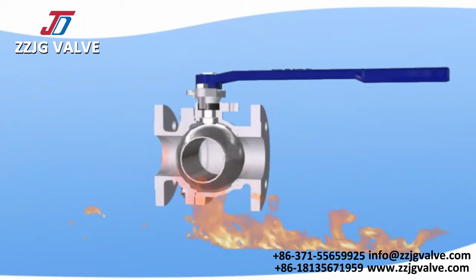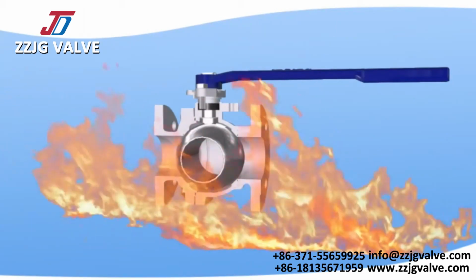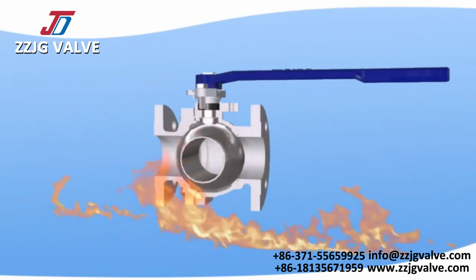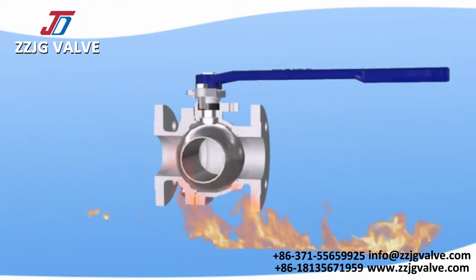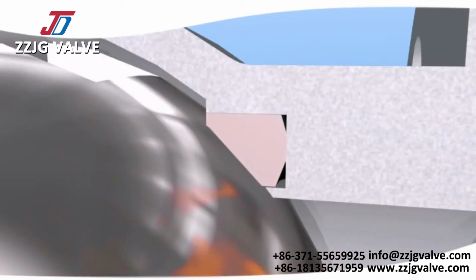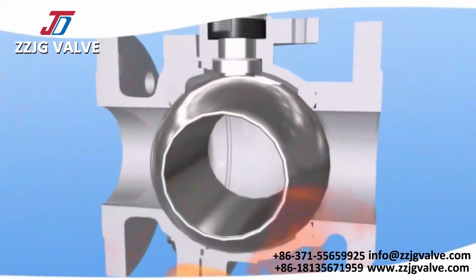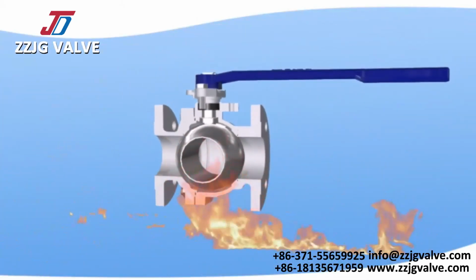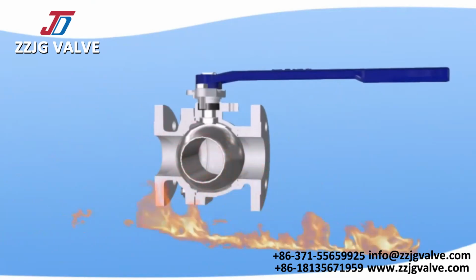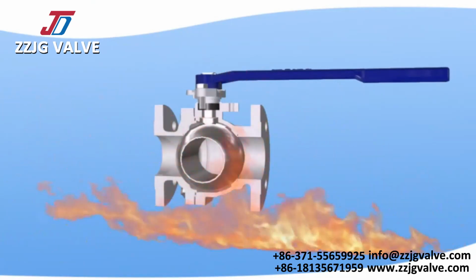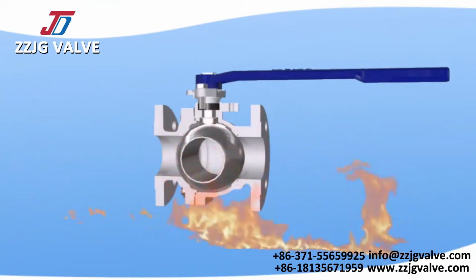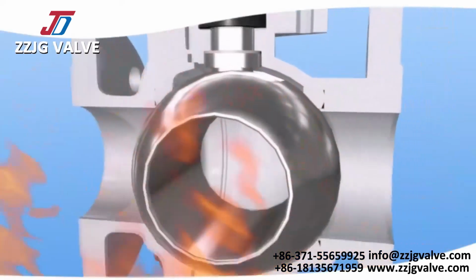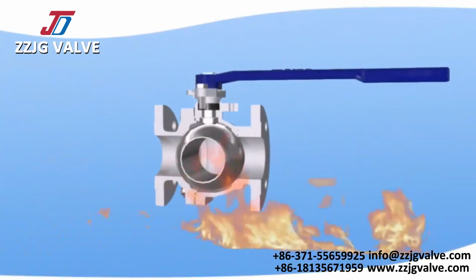5. Fire protection of the seat. In case of fire, the non-metal material of the seat will be burned. Extensive medium leaking may cause fire to spread. The fire protection structure prevents the medium from leaking heavily. The ball valves made by VARC are provided with a metal fire protection layer on the seat face. Once the seal is burned, the ball will directly contact the metal face of the body, thus preventing medium from leaking out. The valve fire protection structure design is according to API 607, API 6FA.